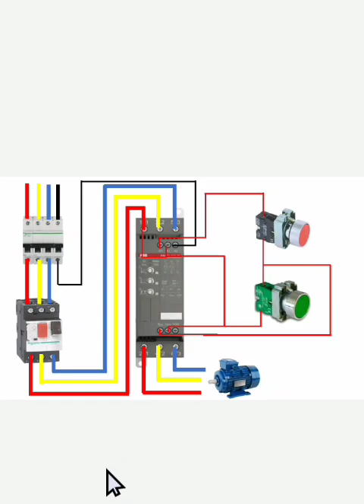For the circuit breaker, it has to be a little bit above the current rating of the motor. Say if your motor is rated 20 amps, 15 amps, or 10 amps, you can use a 32 amp circuit breaker here, and it's a 4-pole.